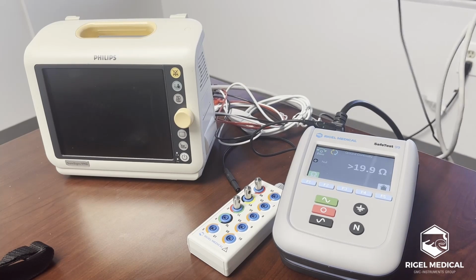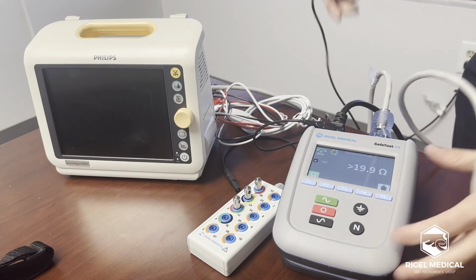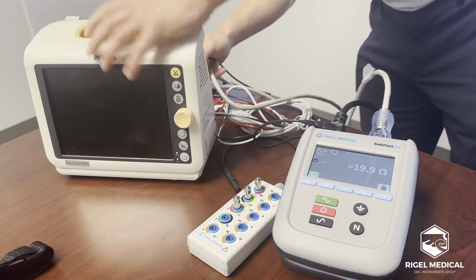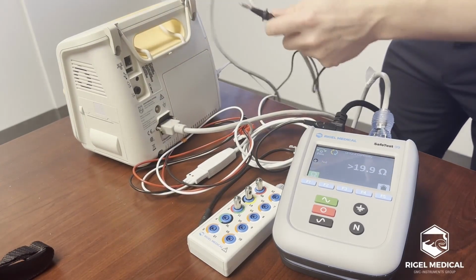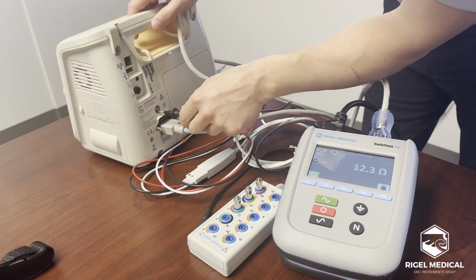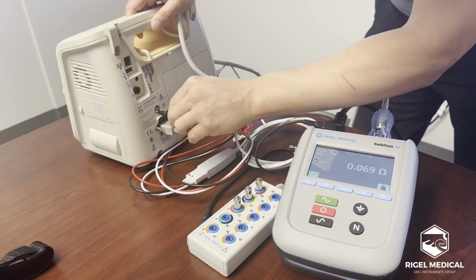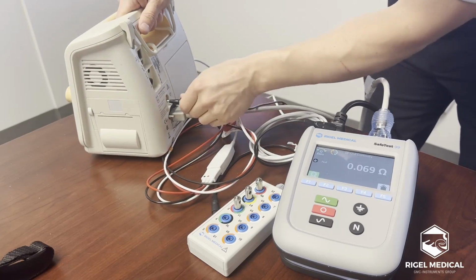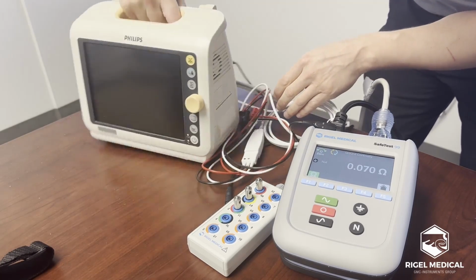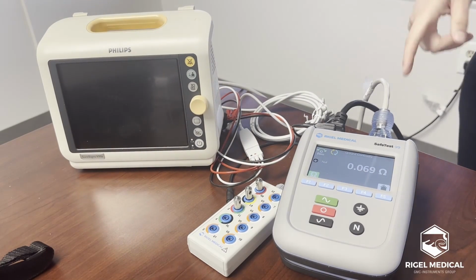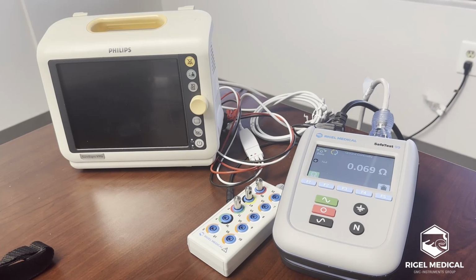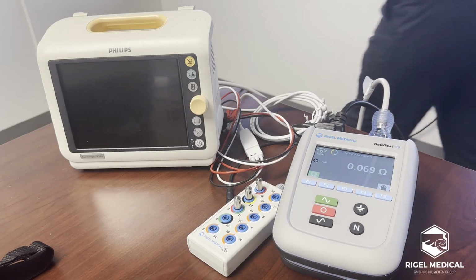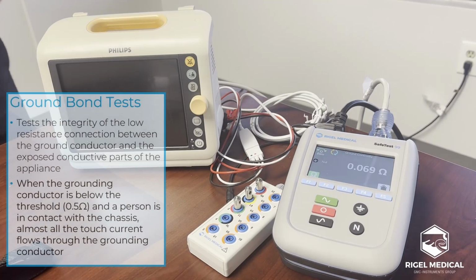So my device under test plug goes into the receptacle of the SafeTest 99, and then I plug the 4mm probe into a point where I'm going to get a good connection. So, well, that fits in there quite nicely. There's a good connection, so I don't even need to hold that on there. It's in there quite snugly. And then I'm looking at the result here, 0.07. So I'm going to pull up some of the slides from our NFPA 99 presentation. So you'll see on screen ground bond tests. As long as the threshold is below 0.5 ohms, then we can prove that it's a pass.